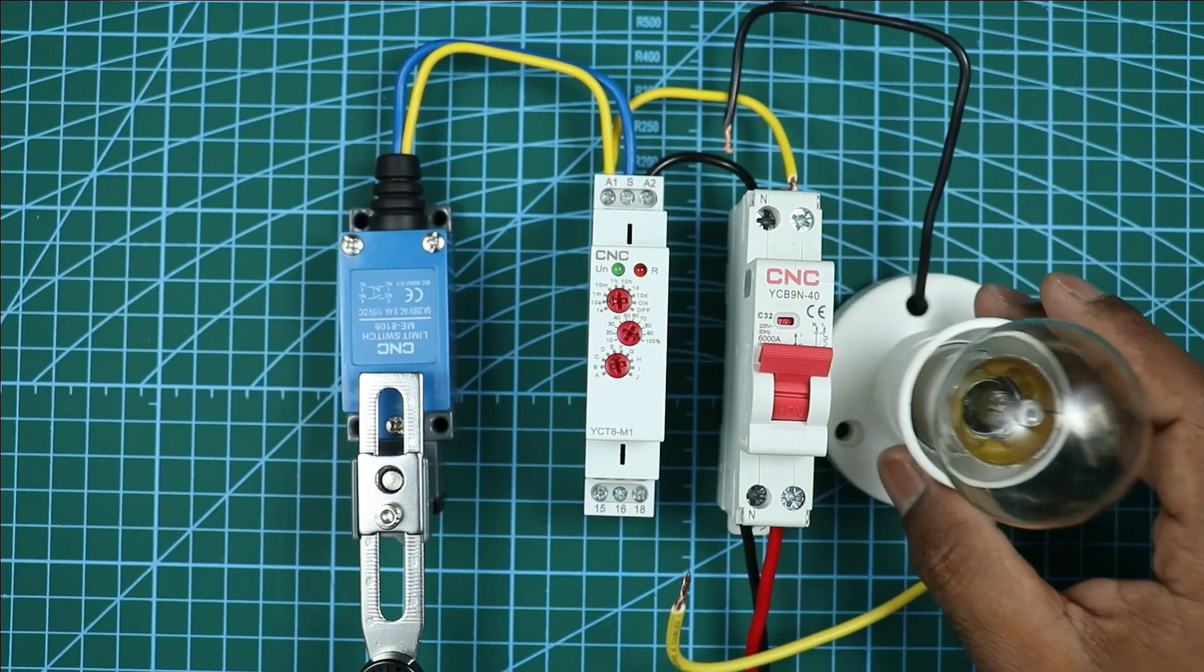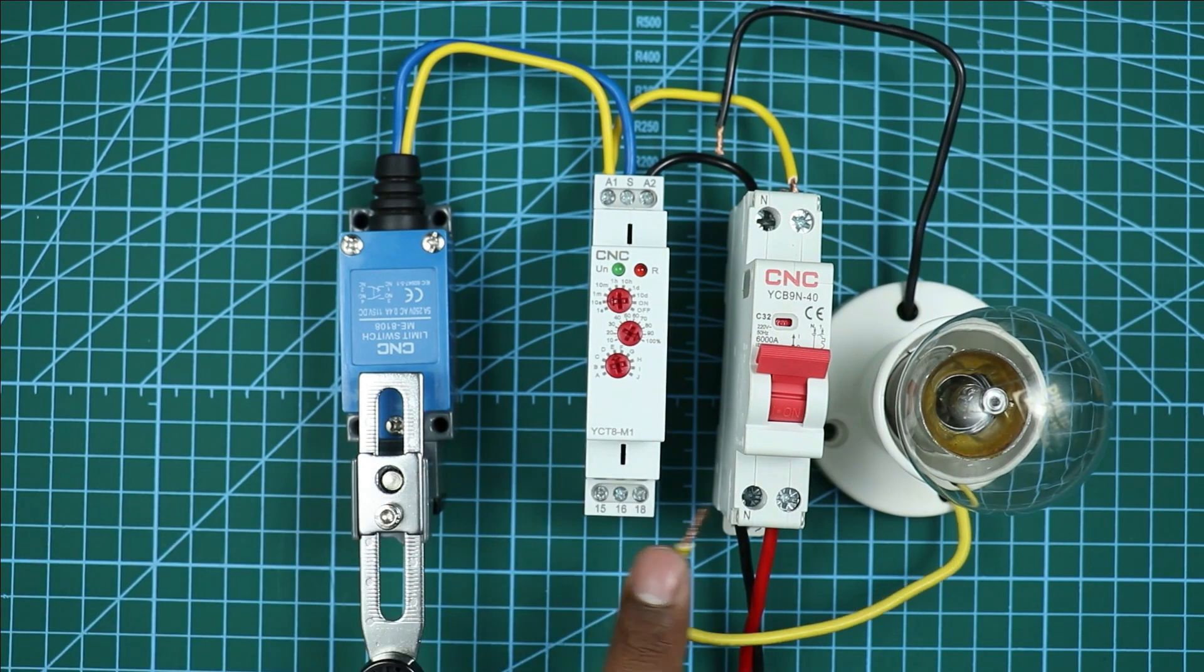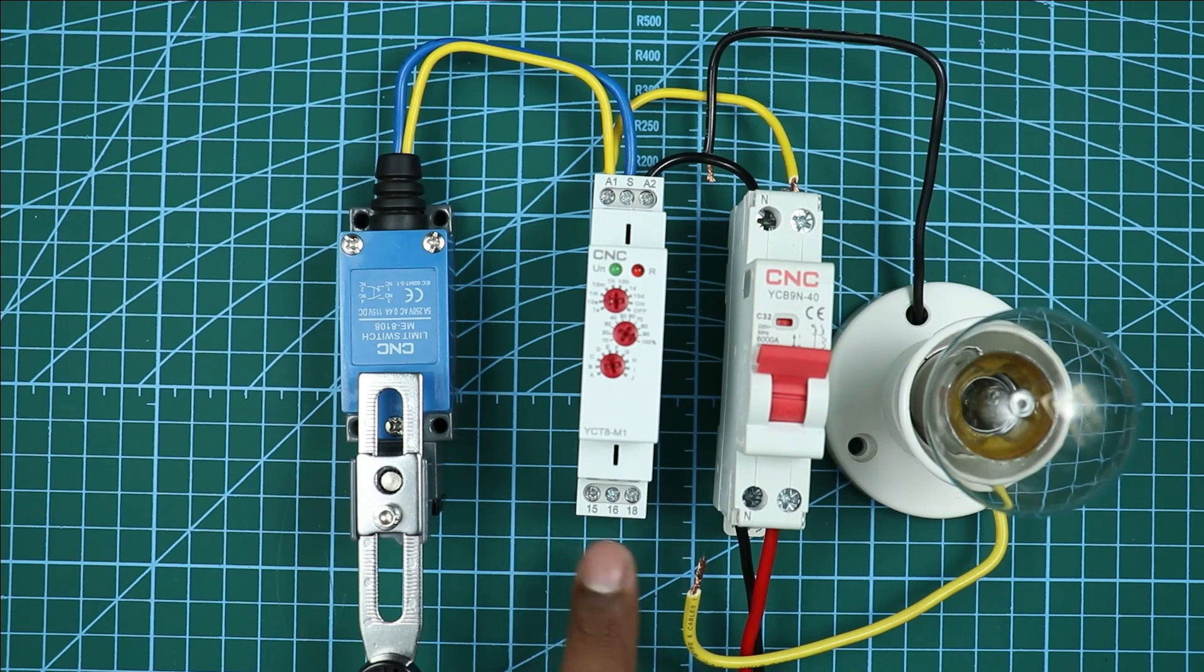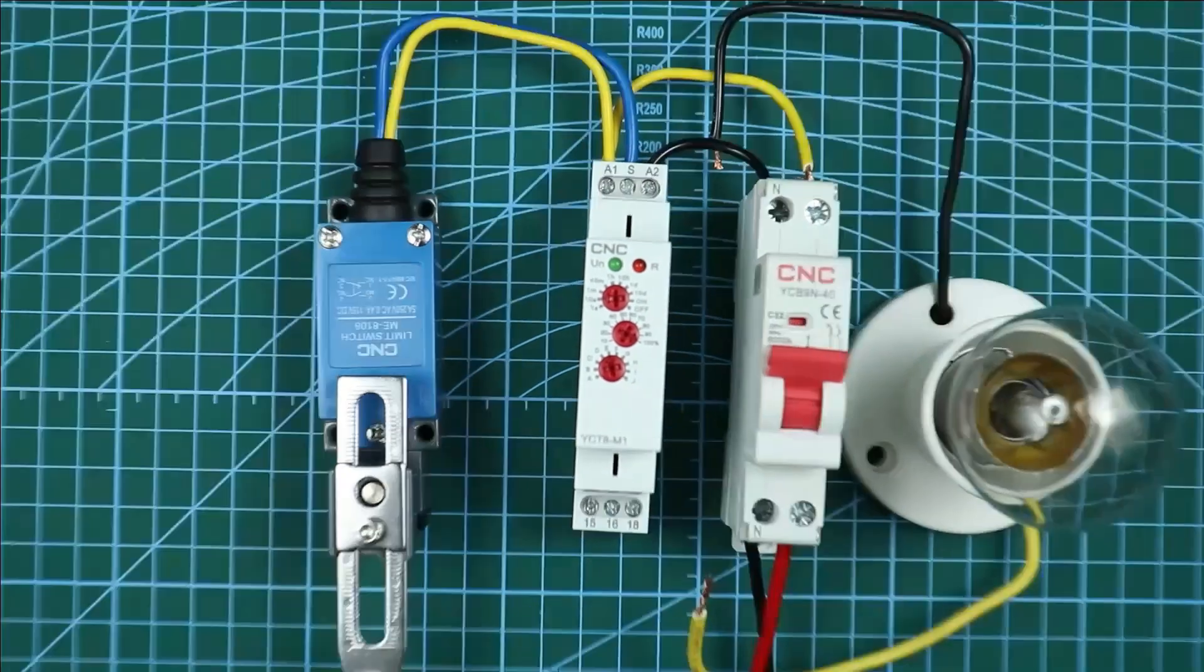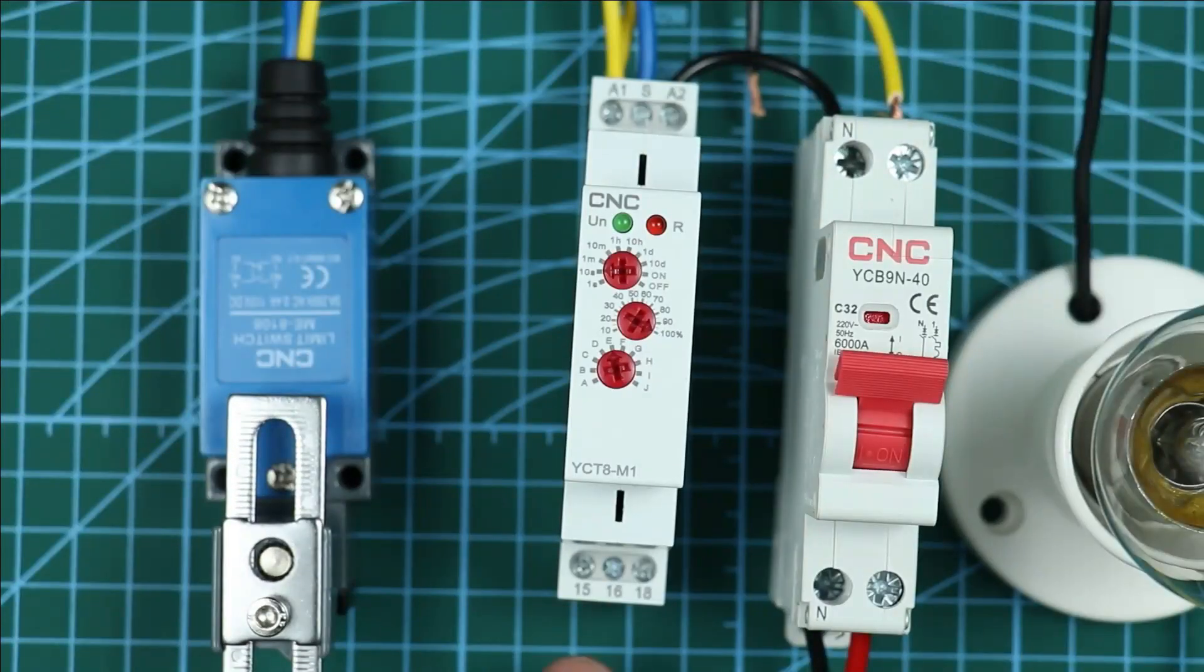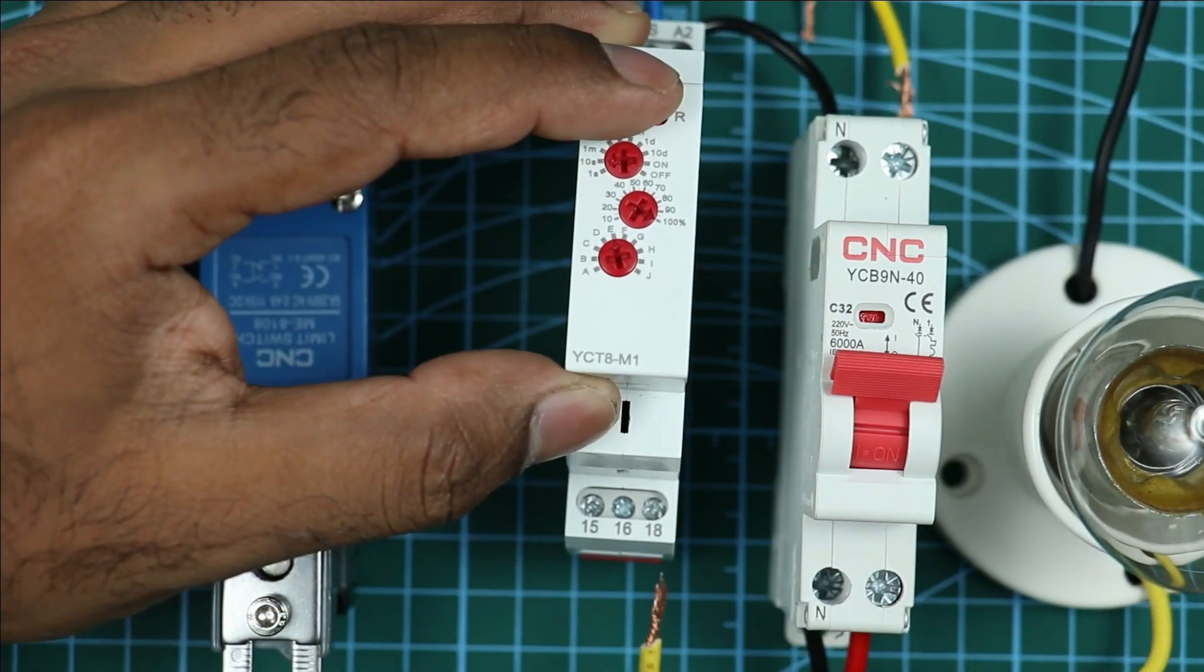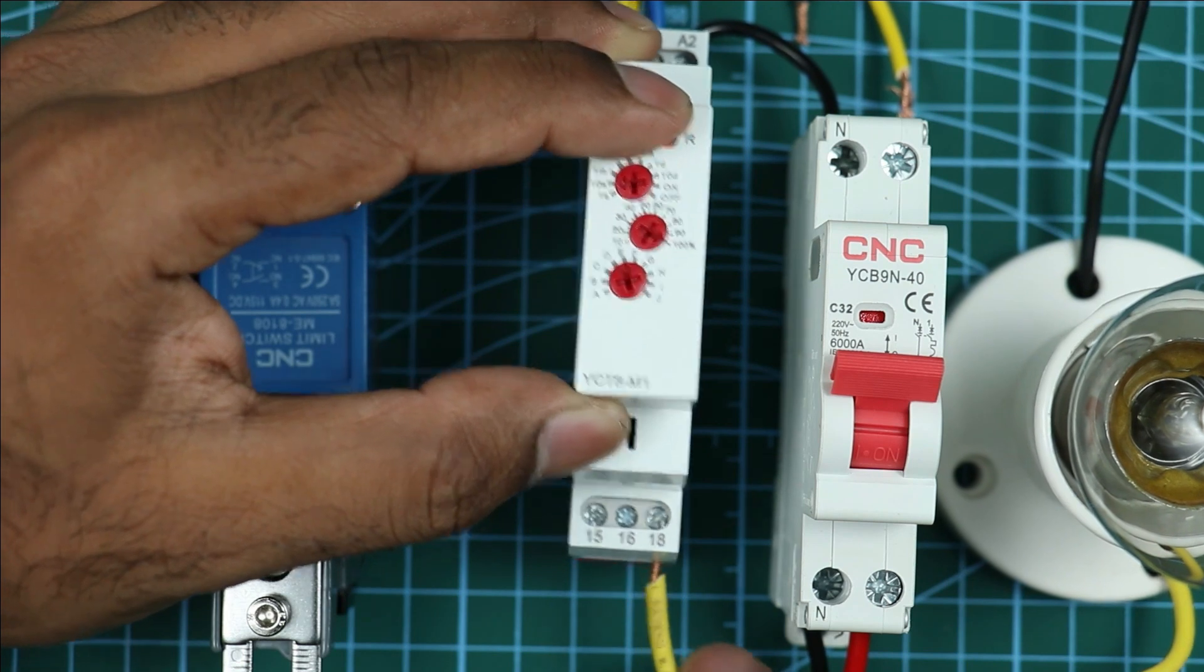Now I want to glow this lamp through this timer. For this, you have to use the NO contact of the timer. When you look at this timer, here 15, 16, 18 - three terminals are present. Among these, 18 and 15 number terminal is for NO contact. What I will do is phase supply wire of the lamp is to be connected with 18 number terminal of timer.